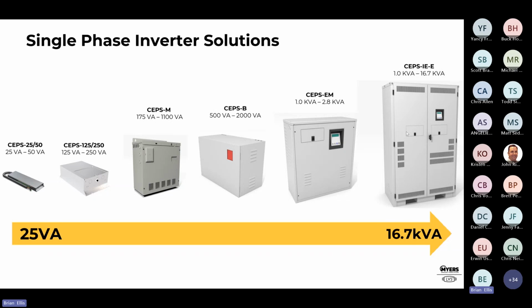On the left over here, we have what we call our micro inverters. So the 25 watt, the 50 watt, the 125 and 250. These are unique in that they can bypass a single lighting control zone on their own. They have a switched input. They also have 0 to 10 volt dimming functionality. So instead of being full light output, as we think most of our inverters are always supplying, which is pretty much true, there's now a new class of inverters where we can utilize the dimming functionality of 0 to 10 volt to have a larger load be supplied power from a smaller inverter, thereby saving money and a little bit better installation for your customers. So we're going to touch on that a little bit later.